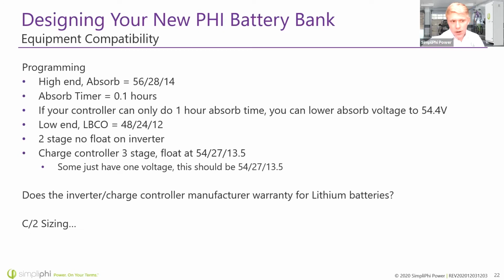Now, another consideration is that we often recommend disabling float on your inverter and enabling float on your charge controller. This is because float is just not necessary on a lithium battery, right? Once it charges full, it really holds on to that charge, whereas a lead acid battery self-discharges quite quickly. I believe it's 5 to 15% per month, depending on the humidity and temperature of the environment they're stored in. Whereas a Phi battery discharges less than 1% per month, so you don't really have to keep it topped off with a float charge. It's just not necessary, but it's not going to hurt the battery. So if you've got PV already coming in, might as well go ahead and use it.